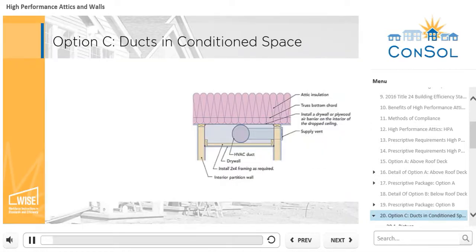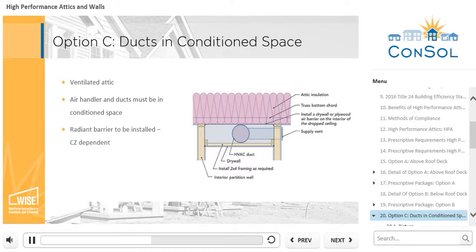An unconditioned attic is the worst place you can put the ducts for your air conditioning. Option C requires a ventilated attic and that the air handler and ducts must be in a conditioned space. In most climate zones, a radiant barrier is required, and, depending on the climate zone the building is in, either R30 or R38 must be installed at the ceiling. Click on the picture for detail of ducts in a conditioned space.